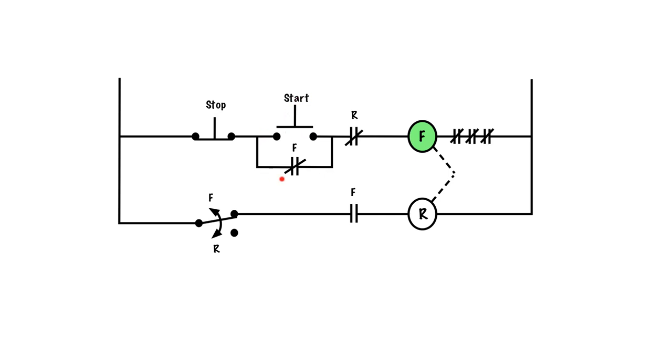So we let go of this, it's being held in, F coil, the motor starts to spin. As the motor starts to spin, the zero speed switch which is attached to the shaft will move into this position here.